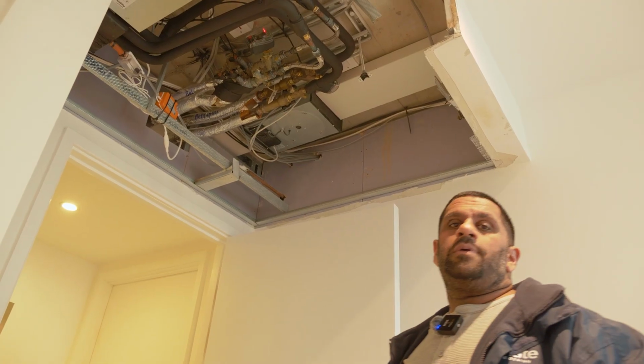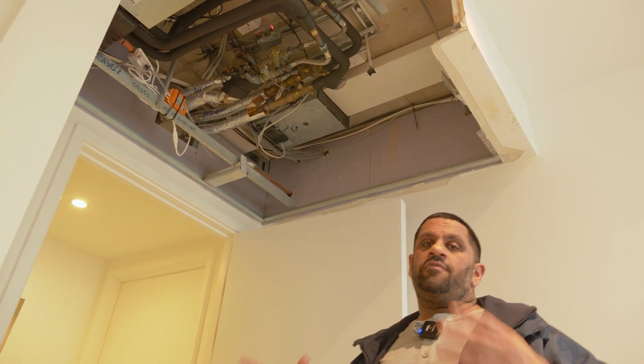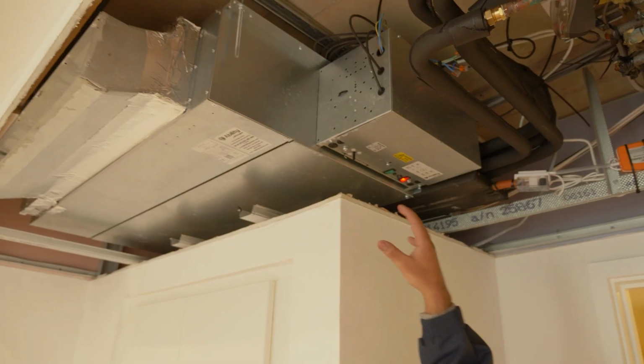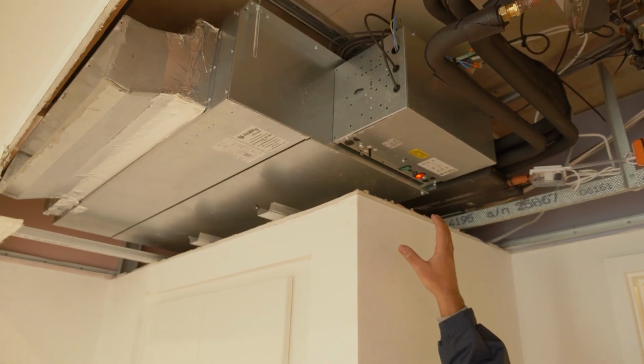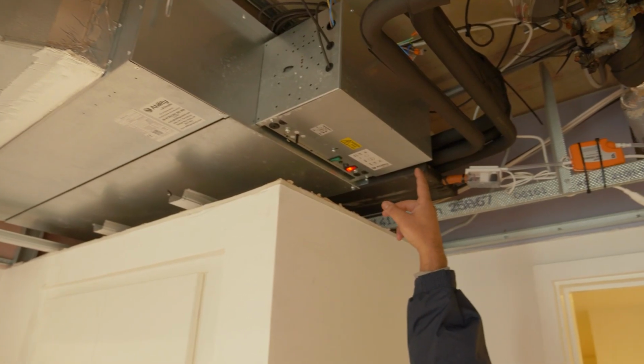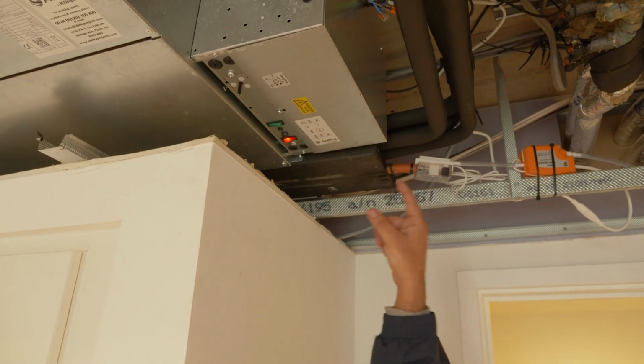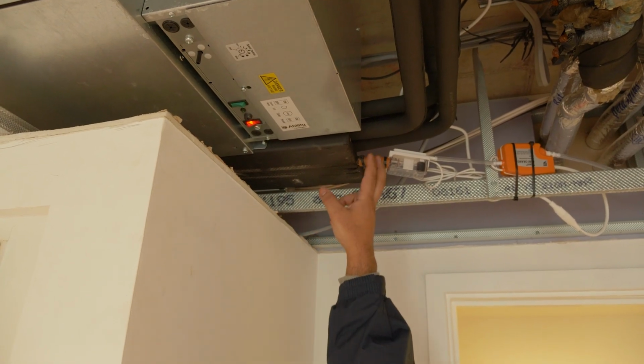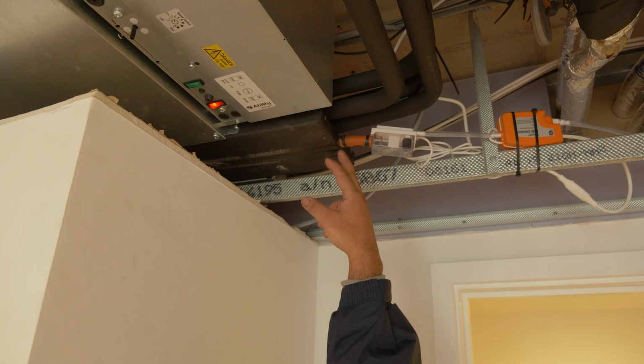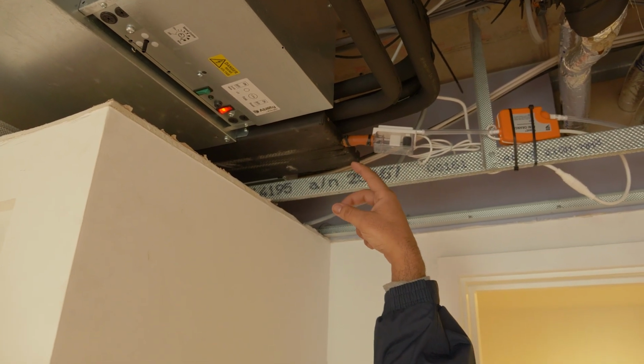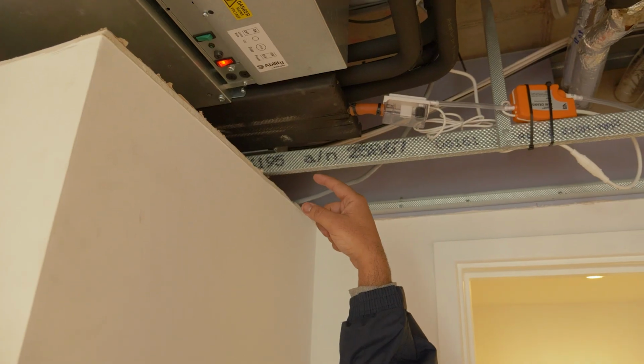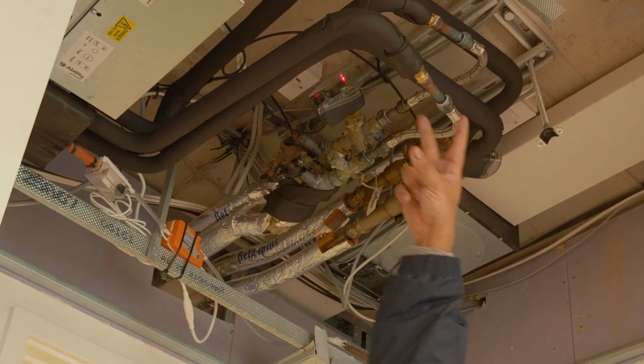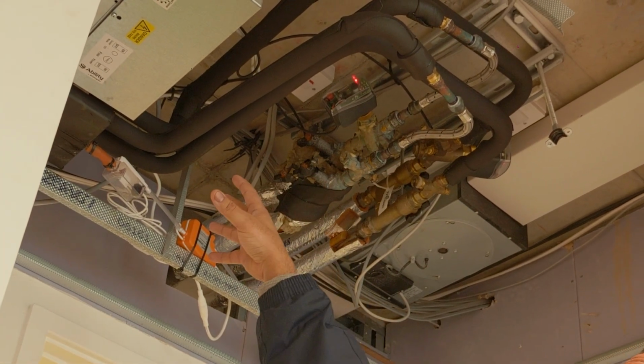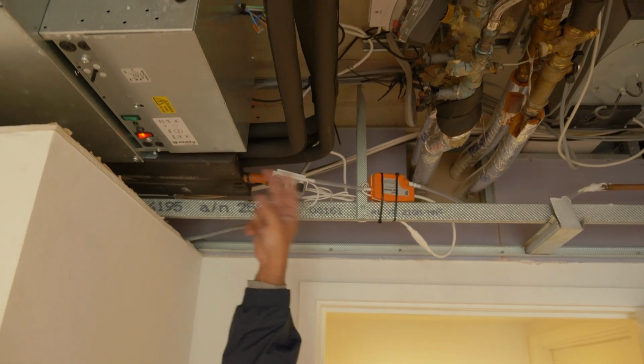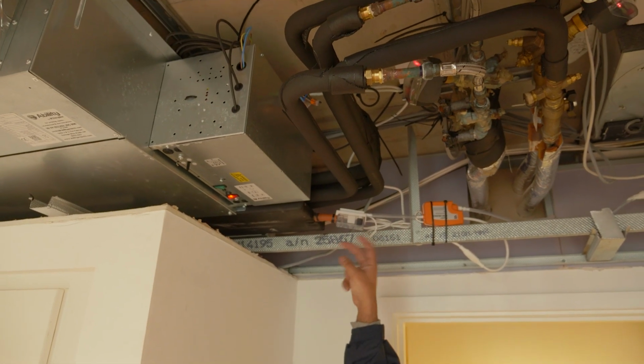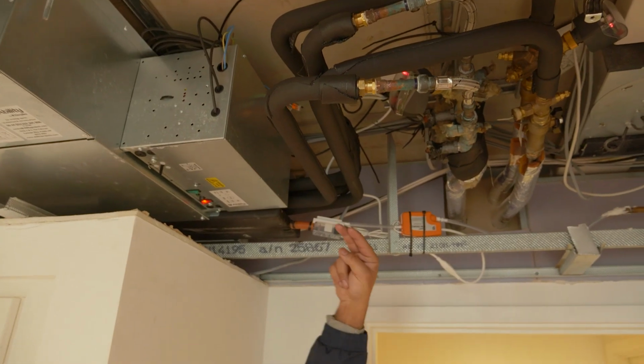So let's go through some of the key components with the chilled water fan coil unit. So we have a fan coil unit, which is the large box, which looks like a typical ducted air conditioning unit. On the side here is the electrical box, which within it has the Delta 5 fan coil unit controller. Here is the extended drip tray. From the drip tray above it, we have the connection points to the heat exchangers that are sitting within the fan coil unit. We have 4 sets of pipes, which you can see here. Our pipes we've rerouted to the back there. These 2 are cooling, flow and return, and the back 2 are heating, flow and return. Flow goes into the bottom, return comes back out.